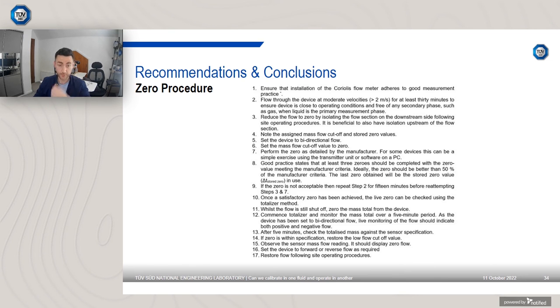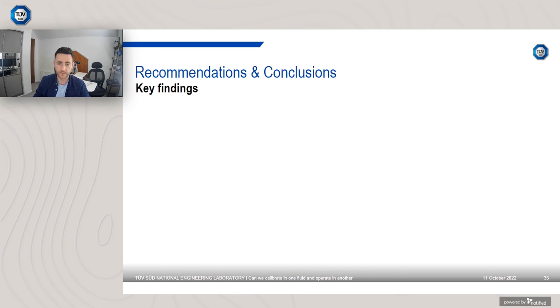So what are my recommendations and conclusions? One of the crucial things for Coriolis meters is to follow the zero procedure. So you should always check the zero, check it with respect to the zero stability. If it's outside the specification or close to the specification, you may want to re-zero. However, if the zero is very good, then you do not need to re-zero it. So this is all detailed here. I don't expect you to read it just now. It's detailed in the NEL Good Practice Guide for Coriolis meters, which I wrote. So if you want to have a read of that, I recommend it. It's freely available on our website. I'll mention it again at the end of the slides today.